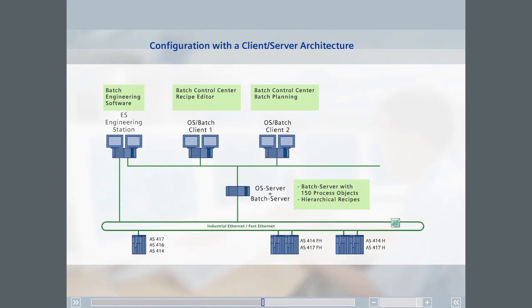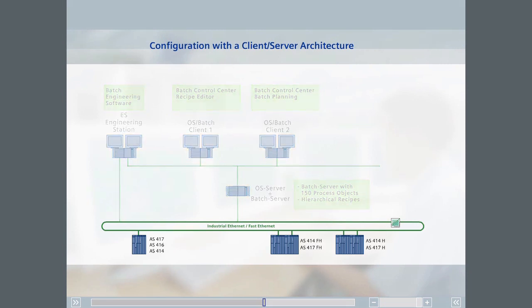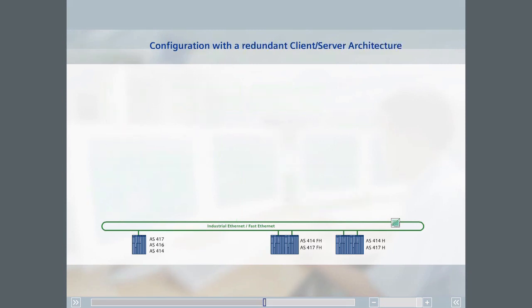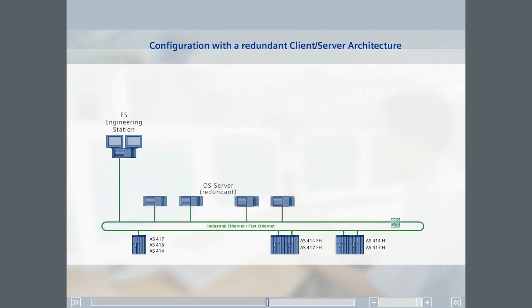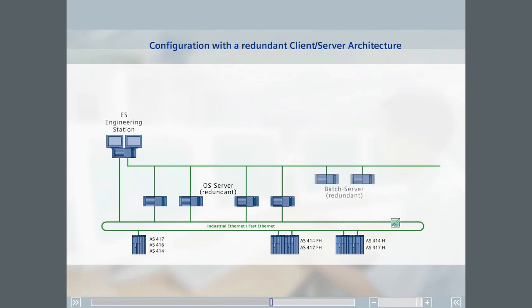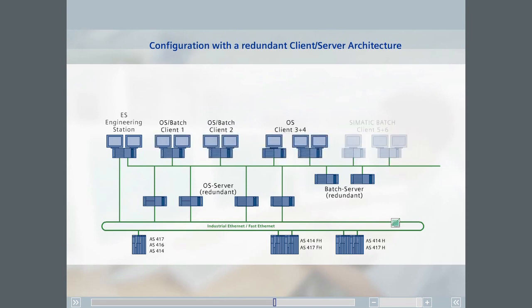In the third example, six operators will control and monitor the system at the same time. The engineering station is once again connected to the automation stations over industrial Ethernet. Due to the more exacting requirements, the two OS servers are set up redundantly. Both pairs of servers are connected to the terminal bus. A redundant OS server setup requires separate batch servers that are also set up redundantly in this case.